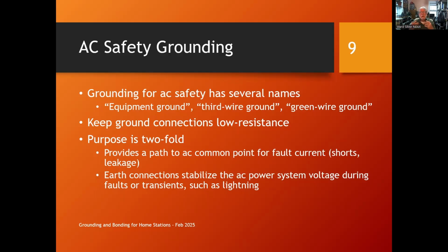Say you have an old radio or something and a bypass capacitor is starting to break down and it allows some AC current to flow through that chassis. You want that leakage current to flow back to the AC common point and not be present as a voltage on that piece of equipment, so you would get a shock.